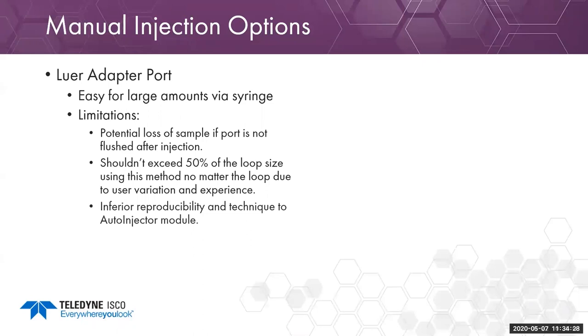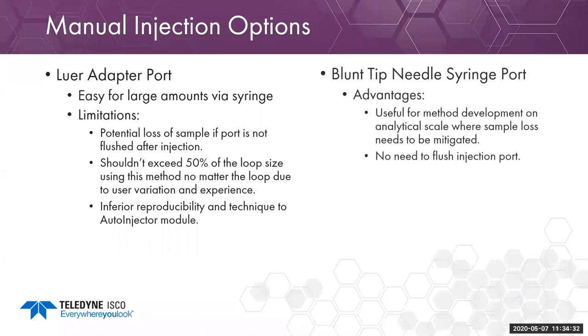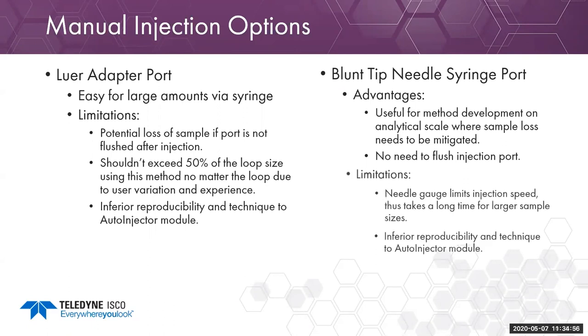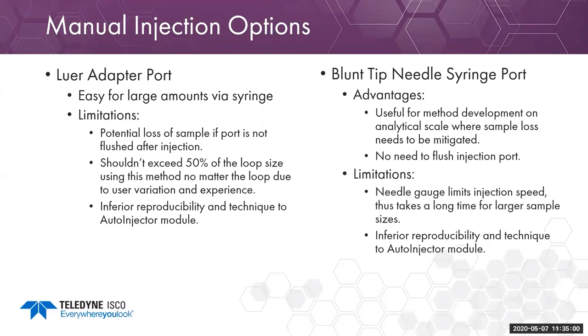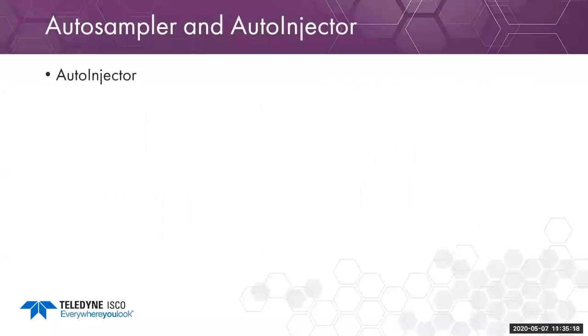Manual injection via luer port has inferior reproducibility compared to auto injection or auto samplers. Another alternative is the blunt tip needle port, which is useful for method development at analytical scale or when sample loss needs to be mitigated, since you inject right at the rotor valve and seal. Limitations include the needle gauge size not being optimal for prep scale injections with larger volumes, and inferior reproducibility versus the auto injector and auto sampling modules.